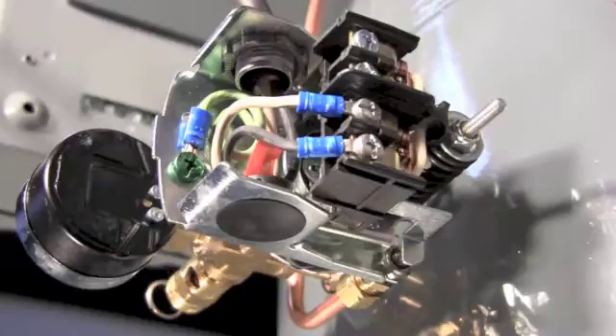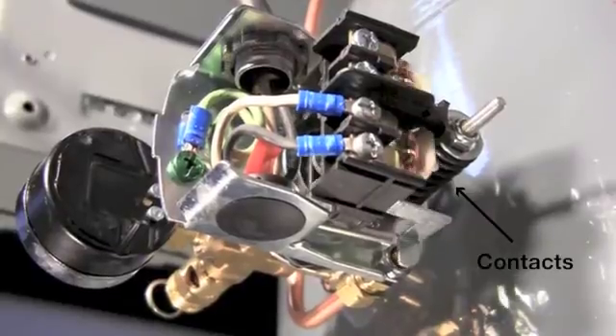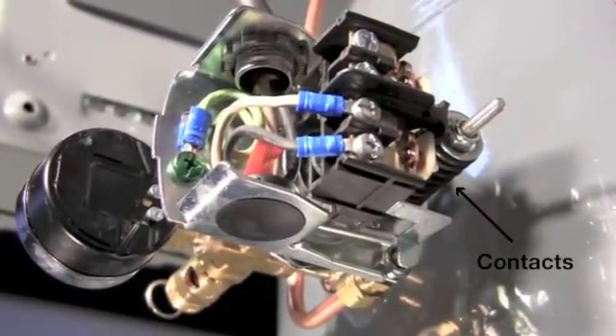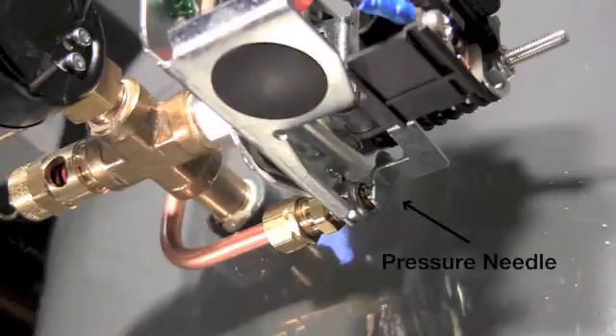When maximum pressure is reached, the contacts located inside the pressure switch open, shutting the motor off and simultaneously pressing down the pressure needle, causing the remaining compressed air between the pressure switch and the compressor pump to purge or blow down.